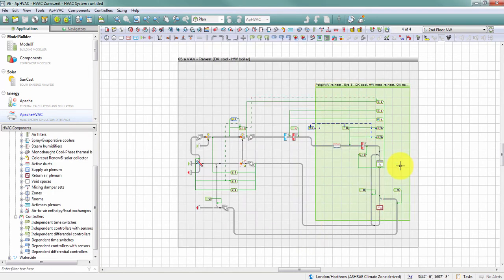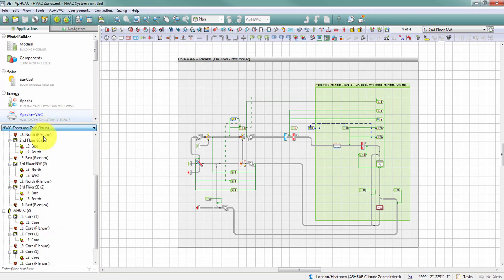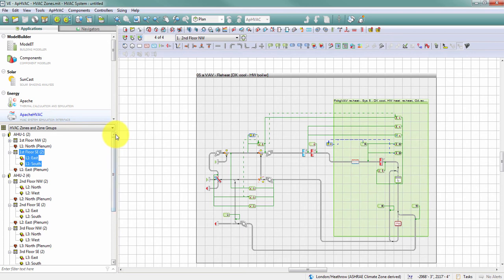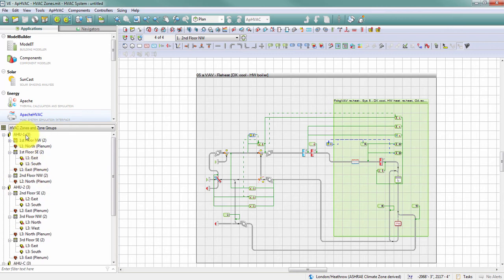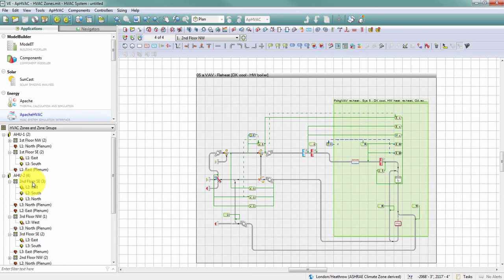If, while you're in Apache HVAC, you want to make changes to either your zones or your zone groups, you can do so without leaving the application. Over here on the HVAC components browser tree, if I expand that pull down menu, I have the option to take a look at my zone and zone groups that I previously defined. I can make changes in here. I can move zones from one group to another, and in this case I'll move it back, as well as I can move spaces from one zone to another zone. A few things to note about making changes to your zones and zone groups while you're in Apache HVAC.